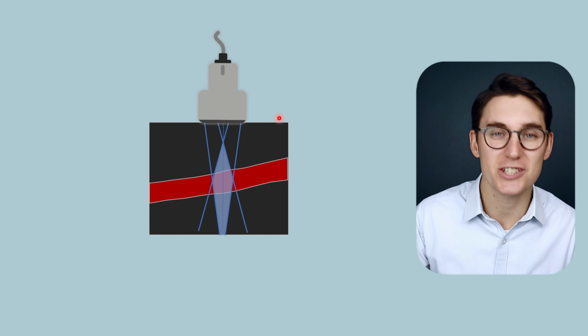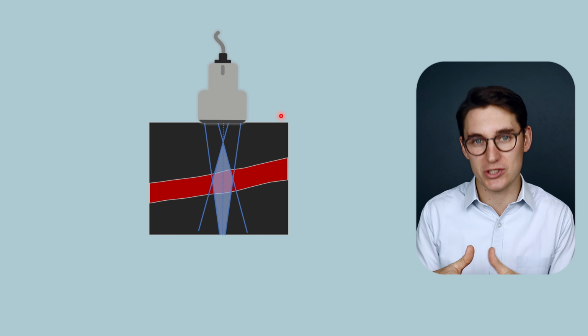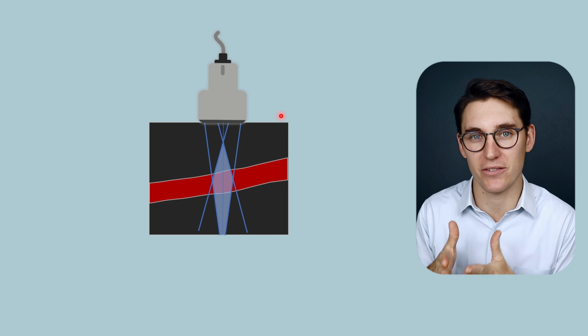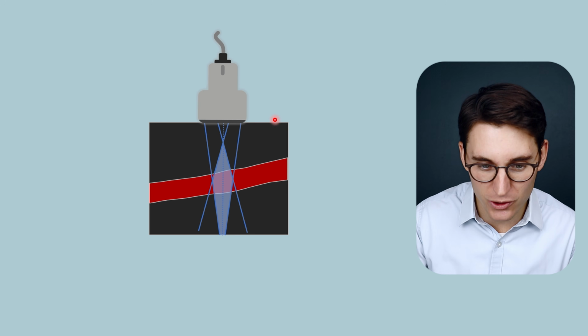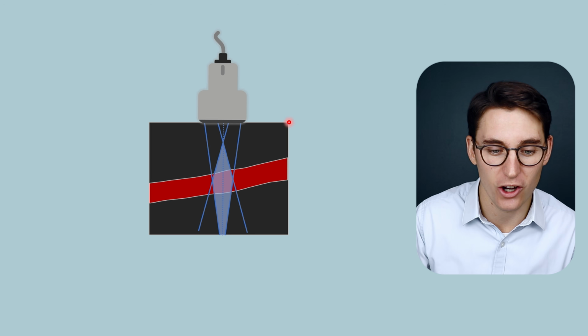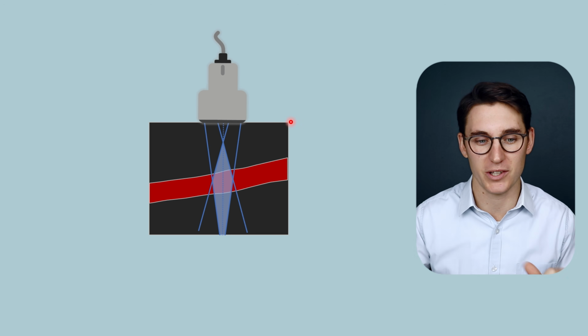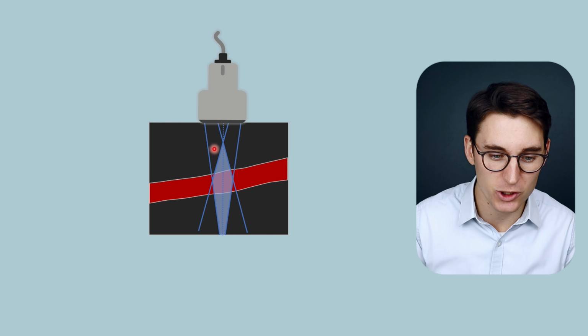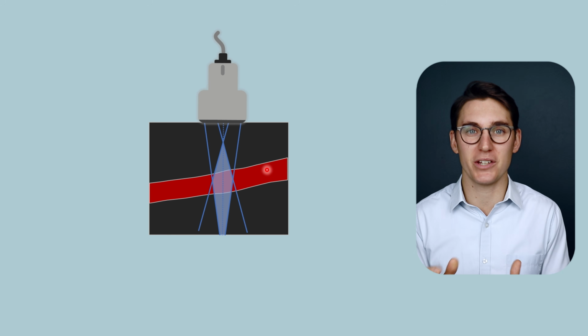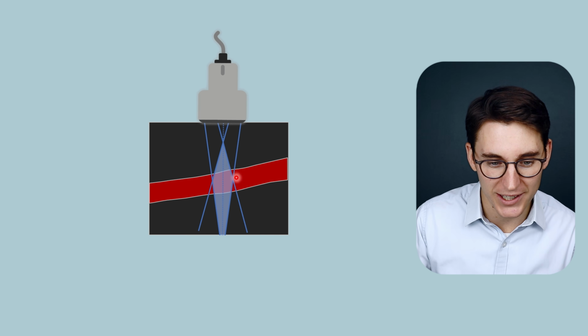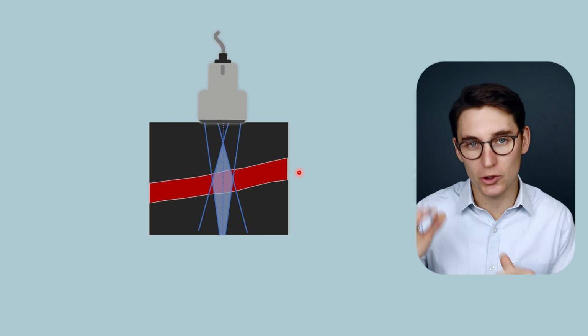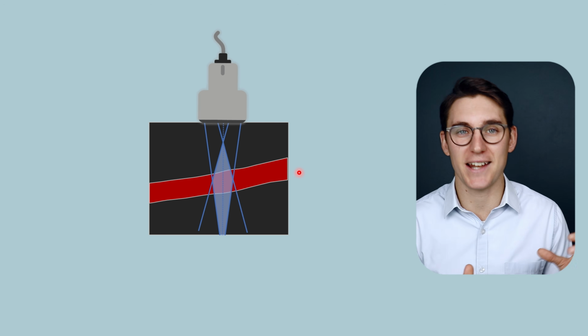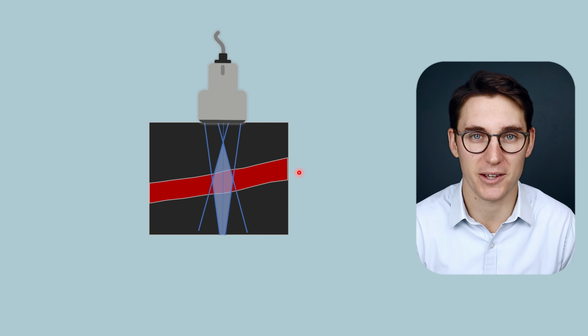Then, two crystals within that ultrasound transducer can act as continuous wave ultrasound probes. The other crystals that lie laterally to this are using pulse echo ultrasonography. These two crystals do exactly what we looked at in the previous slide, but now we can calculate our Doppler angle. And using that Doppler angle, we can get actual velocity values coming back.